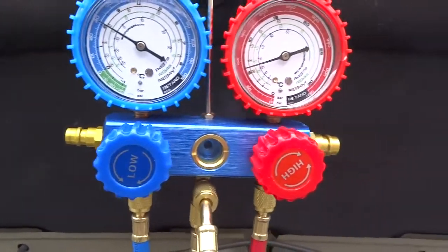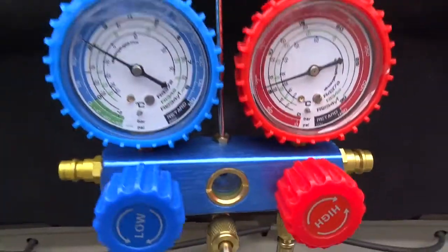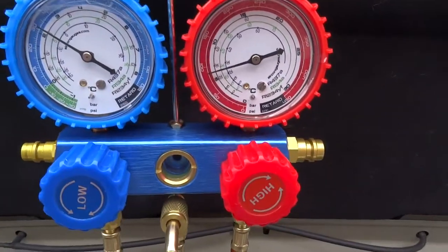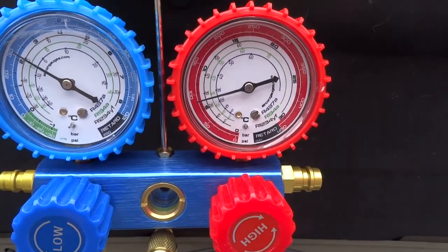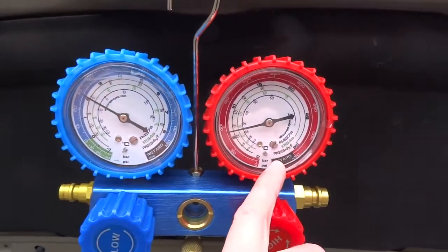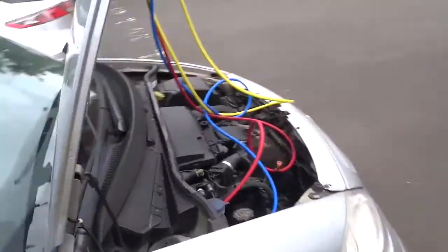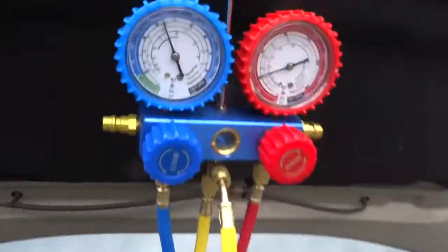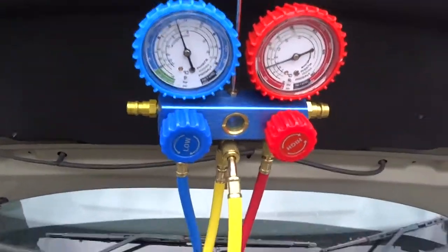So basically we've got 30 on the low side and about 80 on the high. That's really low, so this needs topping up. This is low on gas which is good, so I'll top this up.